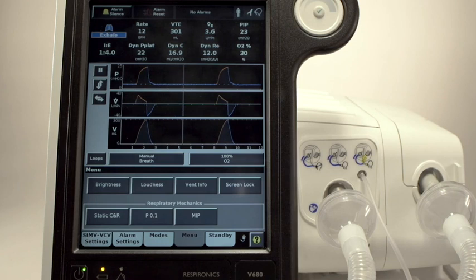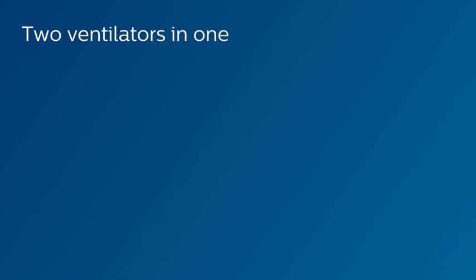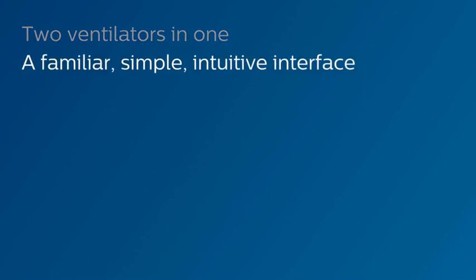Now, let's recap the unique features and benefits of the Philips Respironics V680 Ventilator. Two ventilators in one. A single-limb non-invasive ventilator similar to the V60 with digital AutoTrack Plus. And a dual-limb critical care ventilator with state-of-the-art dynamic respiratory mechanics. A familiar, simple, intuitive interface. If you can operate V60, you should be able to operate V680.